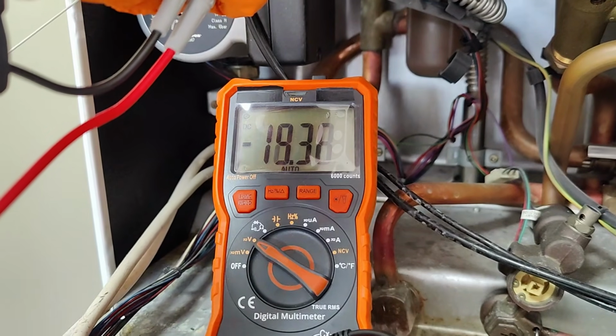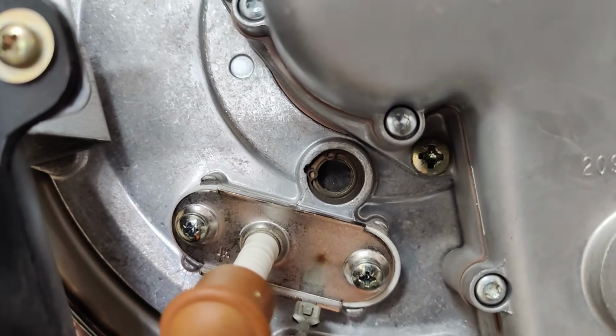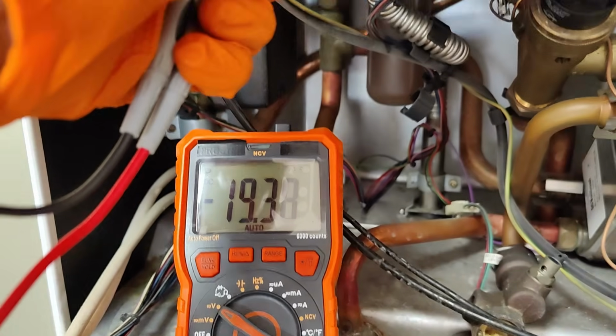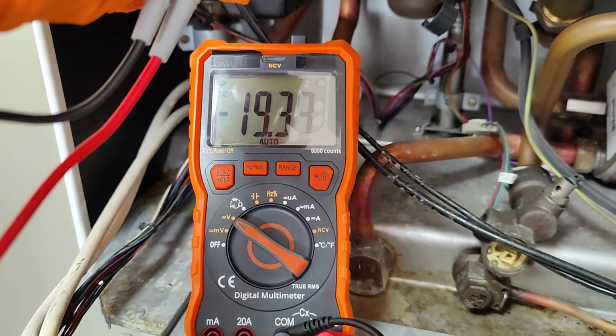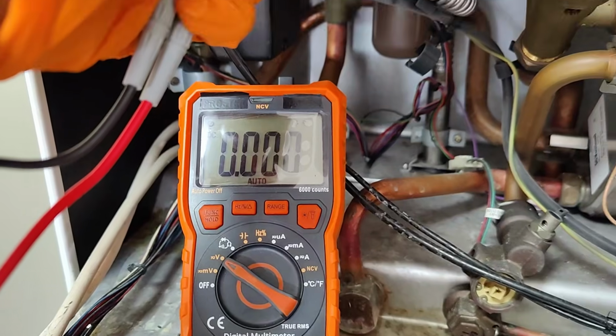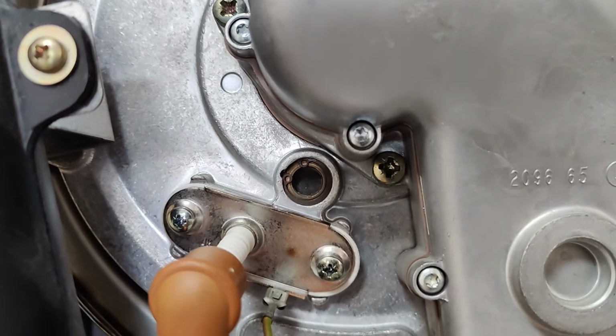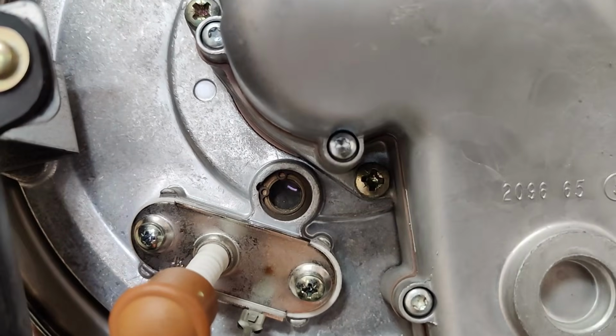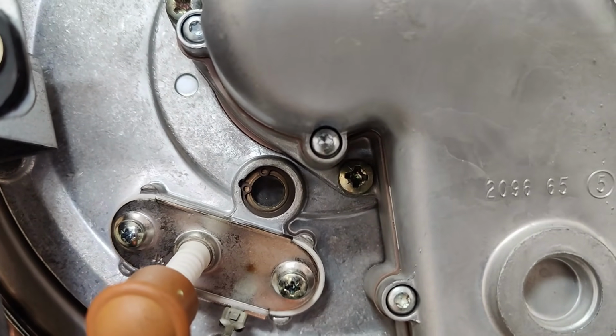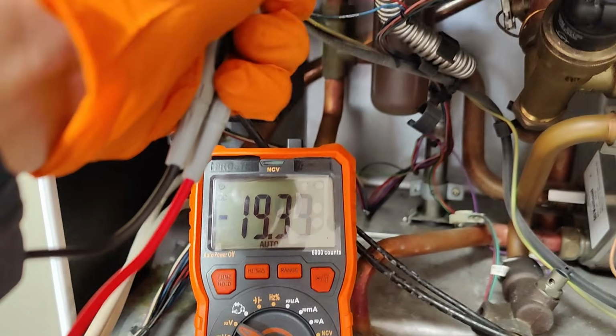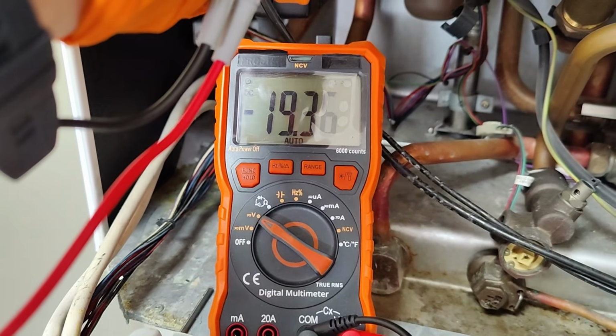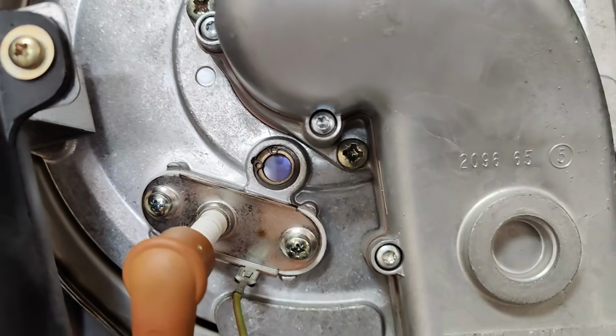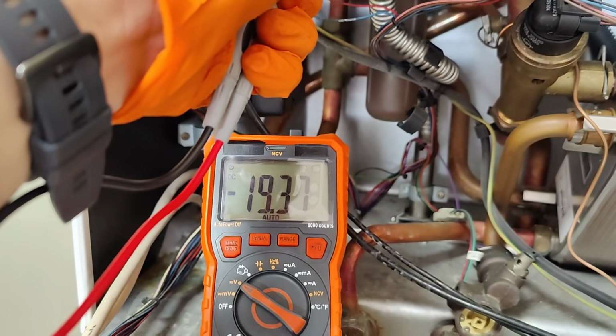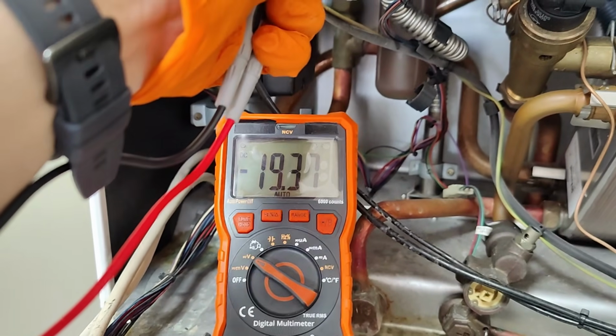So 19.38. It dropped because there's no fire, and it's going to try again. Trying. Voltage is consistent, but I can hear the boiler trying to fire and then it's going out. Let's see if it does it again. There you go. But the voltage remains consistent, as you can see, and now it's starting to work. So I believe it's the gas valve that's faulty. Let's open it up and have a look.